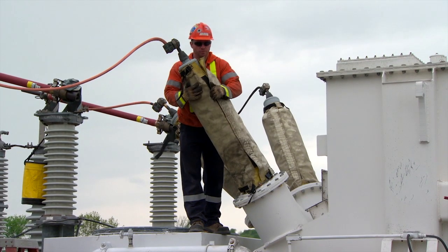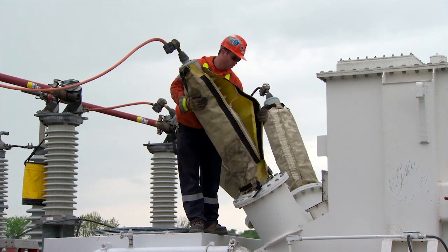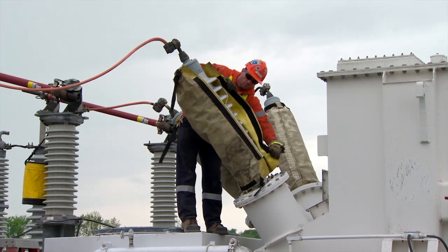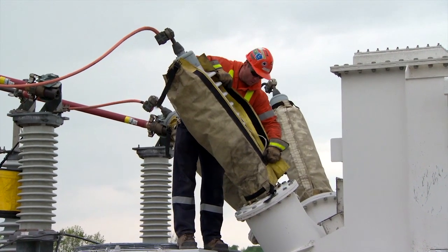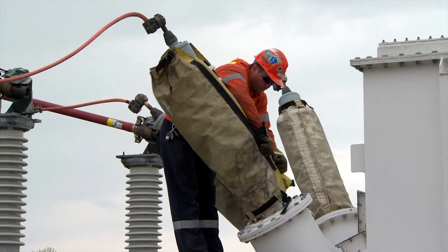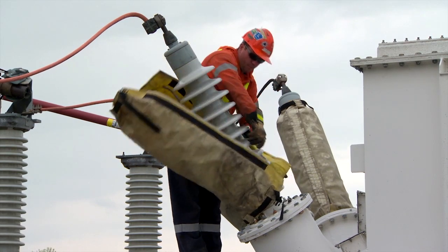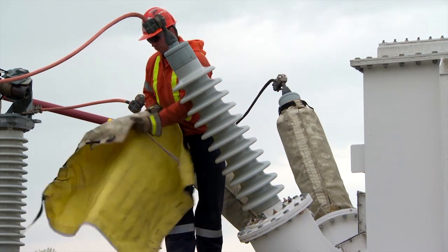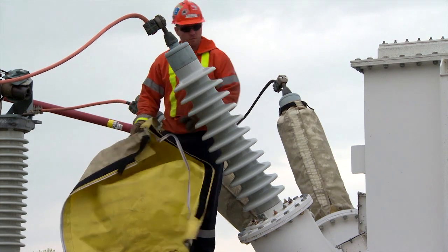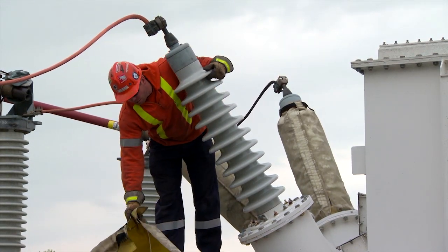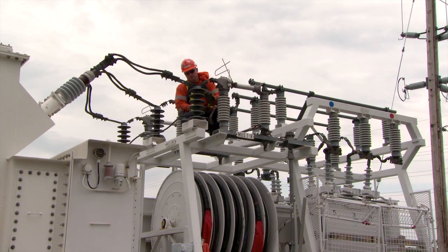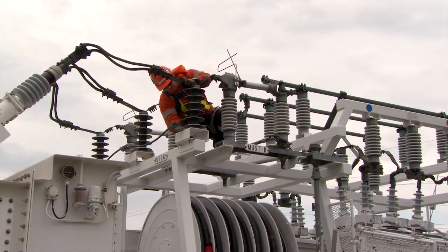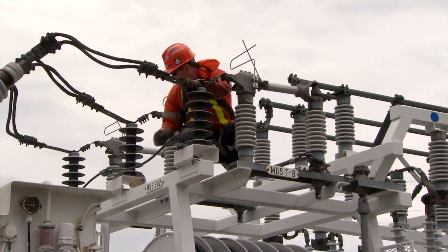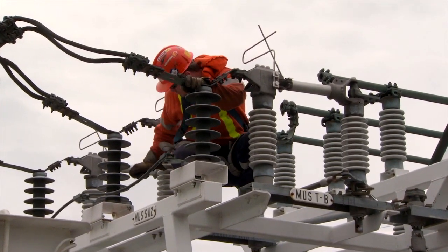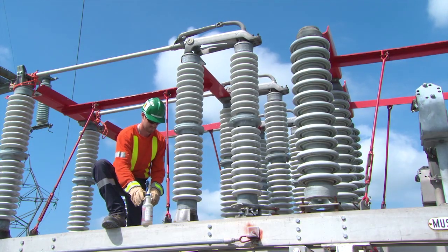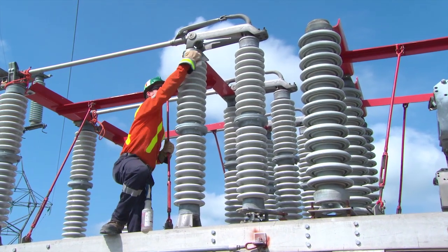Remove the shipping covers on the high-voltage and low-voltage transformer bushings, surge arresters, and gauges. Once all the covers have been removed and stored, visually inspect insulators, surge arresters, and bushings for signs of damage or defect. If required, clean them with isopropanol.